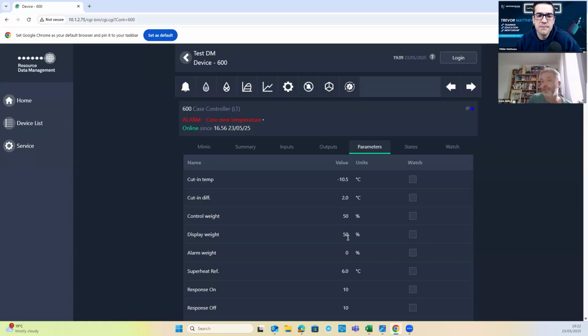Now, your case manufacturer is going to tell you what you want on that. RDM percentages are, your number is the percentage of the air on, right? So if you set that to 100%, it is reading 100% air on, i.e. exactly what the air on probe says. If you set it to 0, it's reading 100% air off. Now, that is the reverse of things like Danfoss, where if you set it to 100%, it's reading air off. So just make sure you set that the right way around.